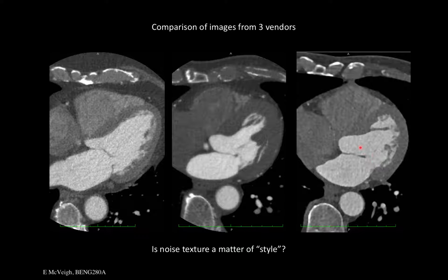This one, God only knows what they do to this picture. They have made these remarkably beautiful edges and really low variance in here. So there's some big shenanigans going on here. This is like a depiction of the object, but it isn't simply a back projection of sinograms. There's no way. There's some really smart stuff. We tried in the lab recreating these pictures from our data, and we went through 20 different algorithms to try and modify sinograms to get pictures that look like this. We could not do it. I have no idea how they do it, and they're not going to tell us.